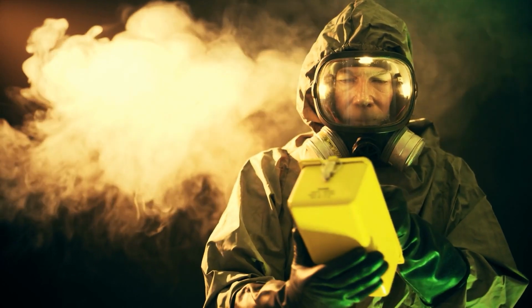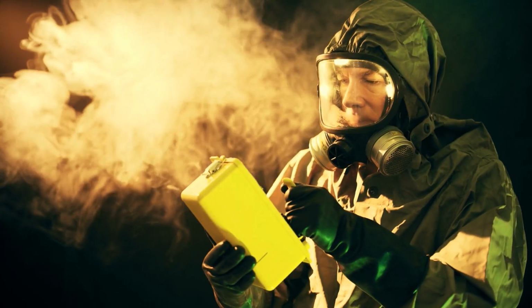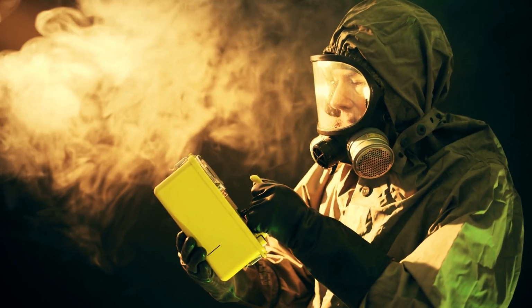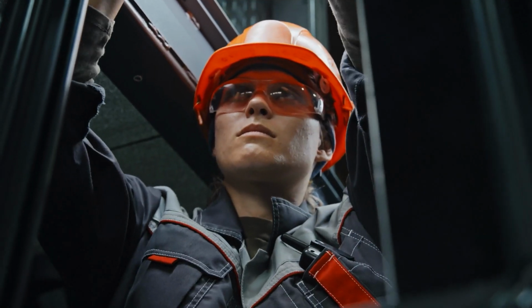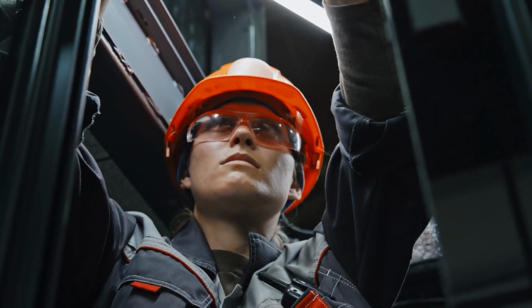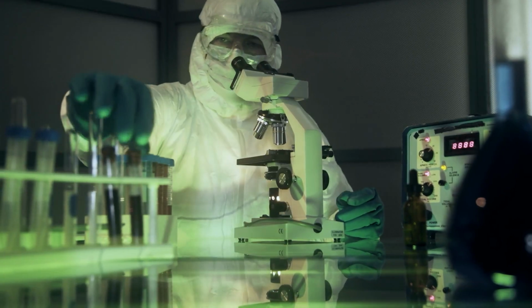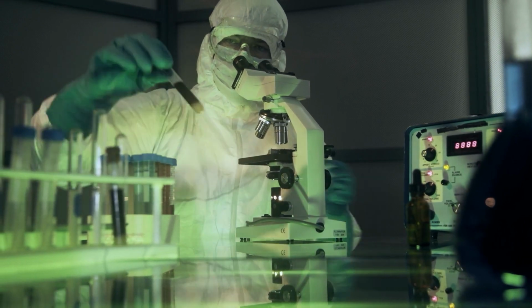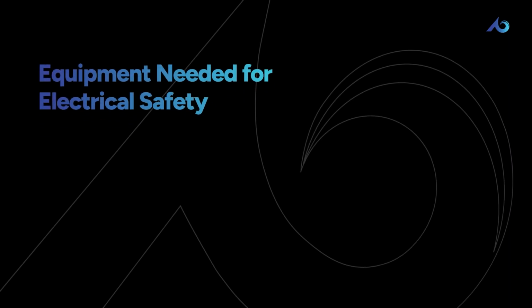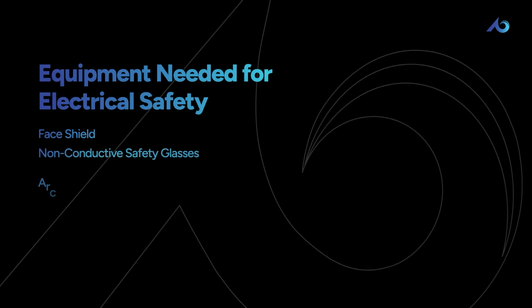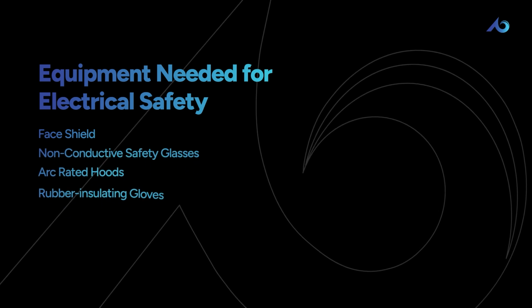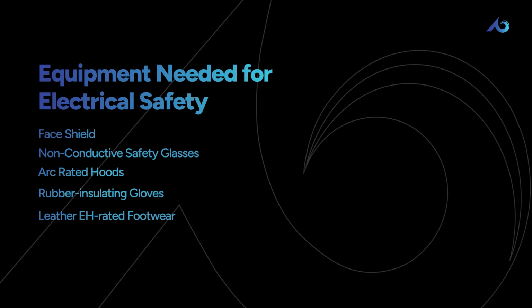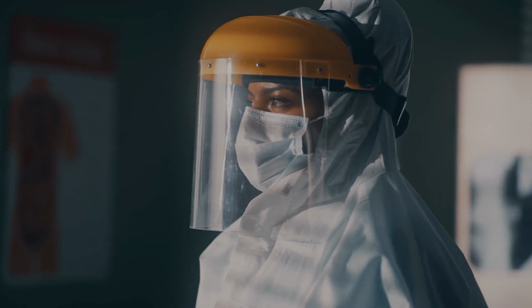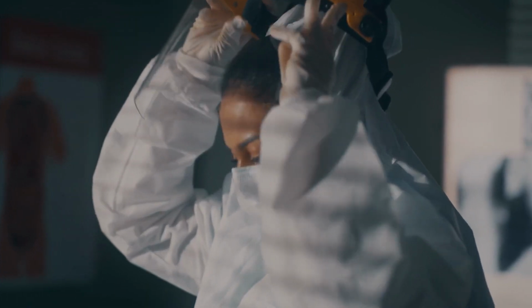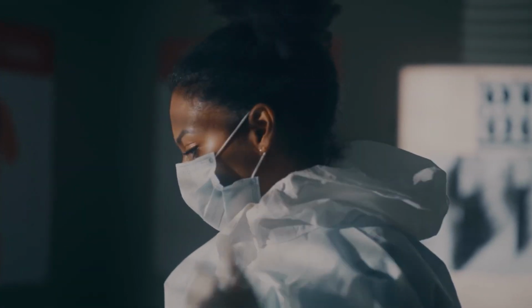Moreover, OSHA has always been firm about the critical role of personal protective equipment in safeguarding workers from electrical hazards. Proper use of PPE can massively reduce the risk of injury from electrical hazards, including electric shock, arc flashes, and burns. Here is the equipment needed for electrical safety: face shields, non-conductive safety glasses, arc-rated hoods, rubber insulating gloves, and leather EH-rated footwear.